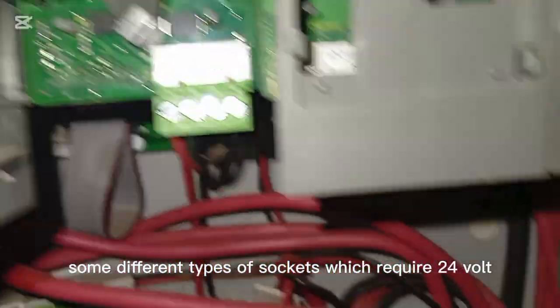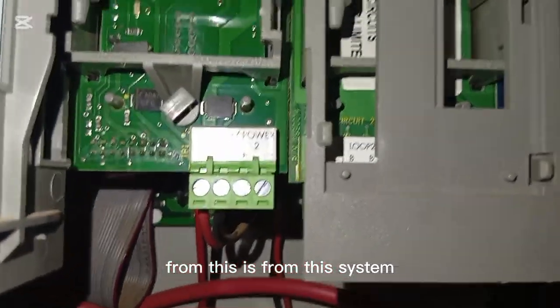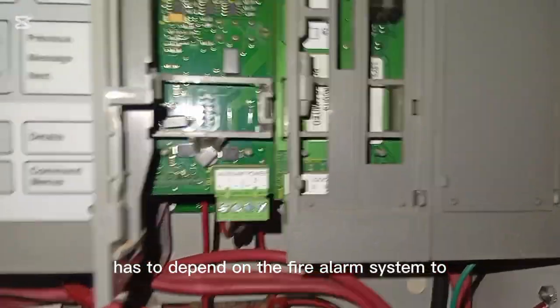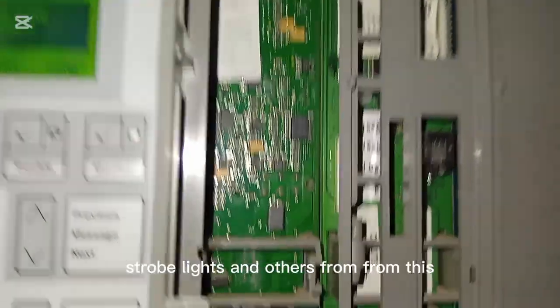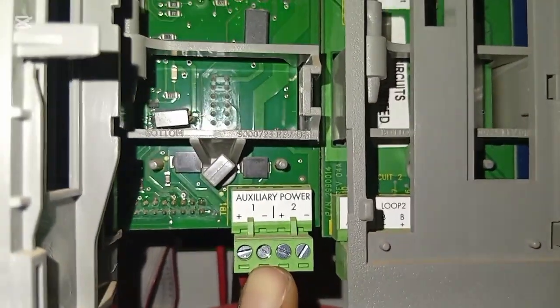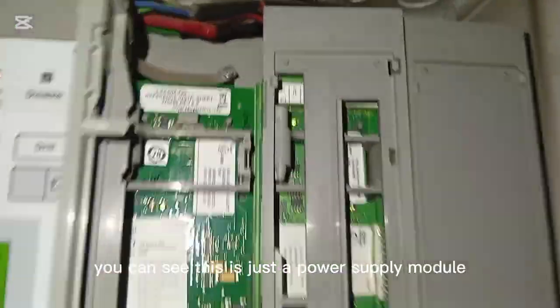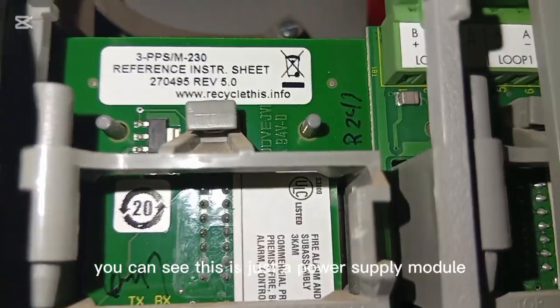Some different types of circuits which require 24 volt come from this system. This is a system that has to depend on the fire alarm system to work, so that in case of alarm panel shutdown, we can still power other circuits like sounders, strobe lights, and others from this card 1. You can see this is just a power supply module. Okay, this is card 1.